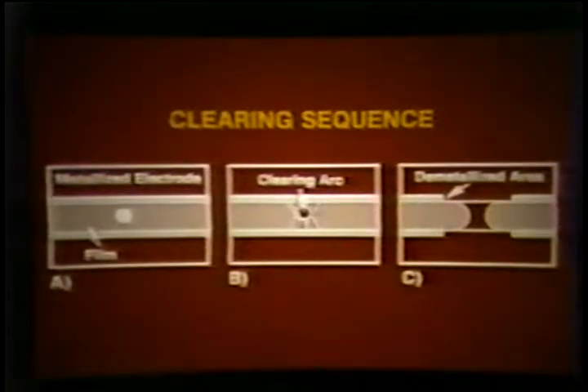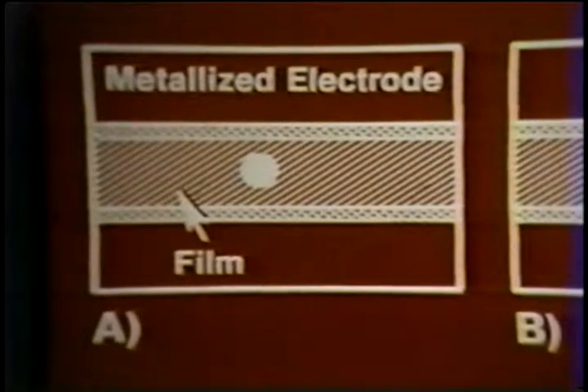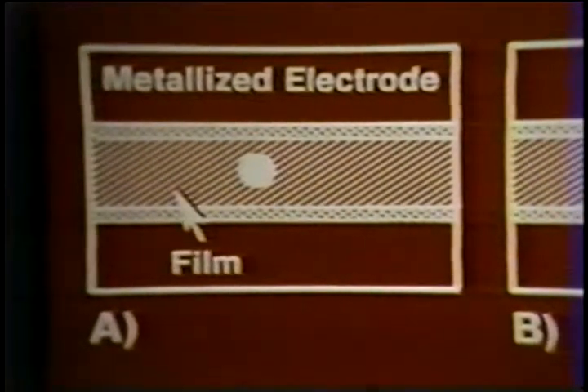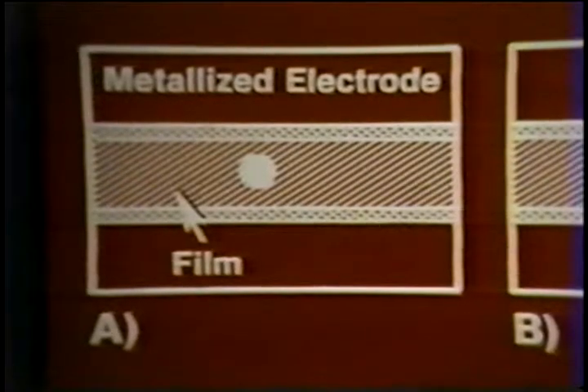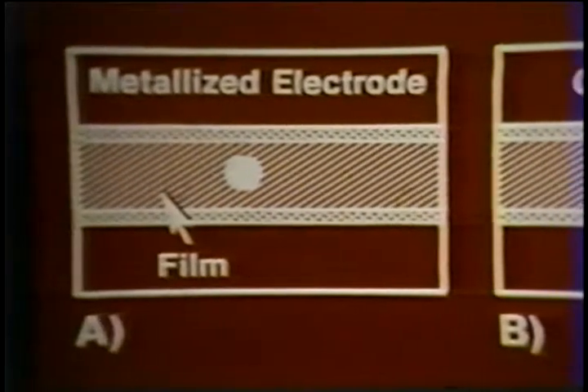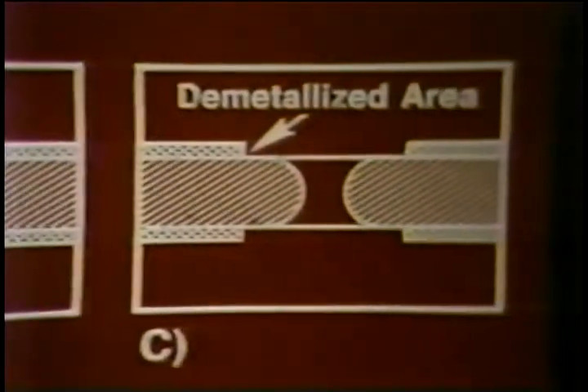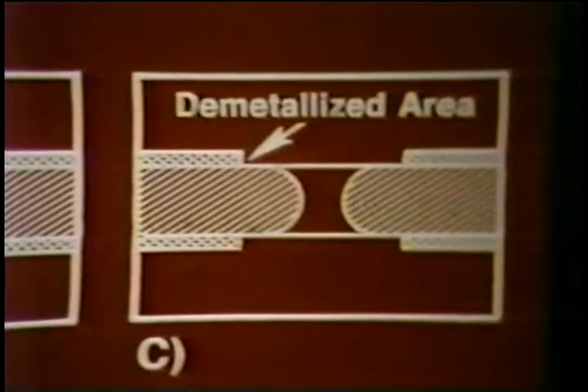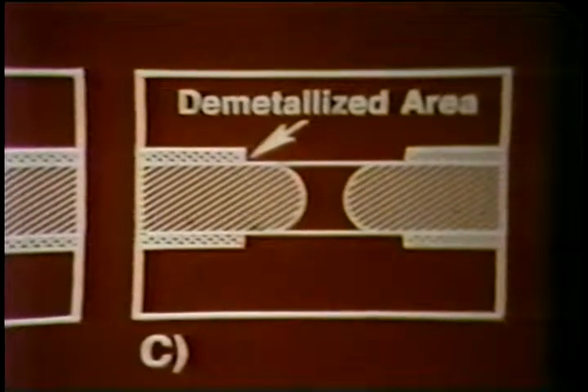On the left we see a dielectric with a defect present. This defect may be a dirt particle, a hole, or a scratch, or any other defect in the dielectric. During operation, this defect can cause a momentary breakdown. An arc can exist between the two electrodes, as shown in the middle. During this arcing, temperatures in excess of 2,000 degrees centigrade can exist in the dielectric, which vaporizes the dielectric and the aluminum electrode from around this defect site, isolating it from the rest of the electrode area.